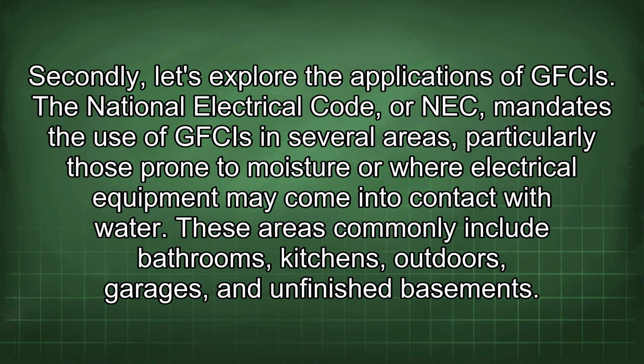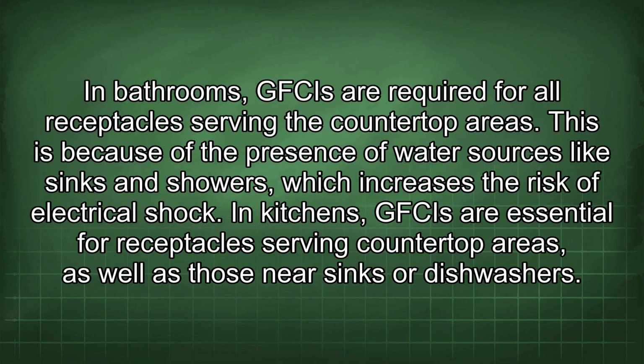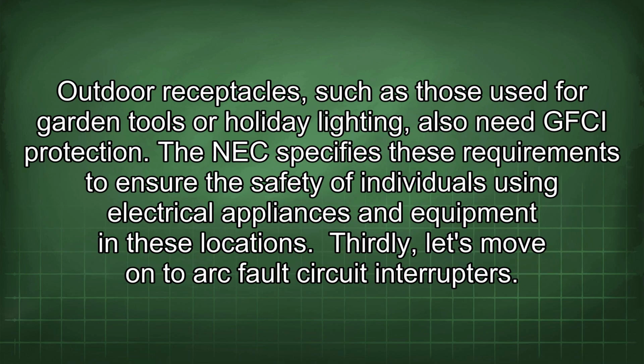Secondly, let's explore the applications of GFCIs. The National Electrical Code, or NEC, mandates the use of GFCIs in several areas, particularly those prone to moisture or where electrical equipment may come into contact with water. These areas commonly include bathrooms, kitchens, outdoors, garages, and unfinished basements. In bathrooms, GFCIs are required for all receptacles serving the countertop areas. This is because of the presence of water sources like sinks and showers, which increases the risk of electrical shock. In kitchens, GFCIs are essential for receptacles serving countertop areas, as well as those near sinks or dishwashers. Outdoor receptacles, such as those used for garden tools or holiday lighting, also need GFCI protection. The NEC specifies these requirements to ensure the safety of individuals using electrical appliances and equipment in these locations.